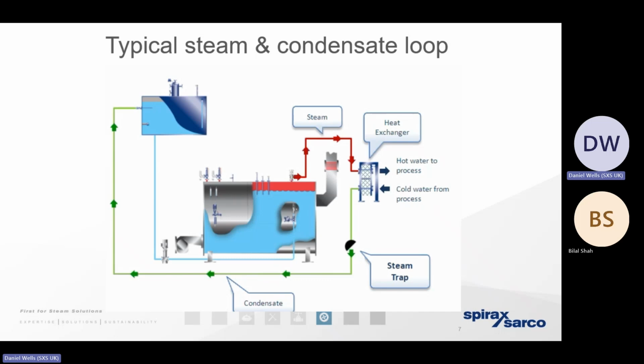very small pipe diameter. So if you think about the hospital up the road, or if you think at the chemical works down on Leeds Road, we could be distributing that steam thousands of meters. So if we can distribute high pressure steam with a small volume in a small pipework, there's a huge financial benefit to us. The other benefit of high pressure steam is we've got a lot of motive energy that is pushing the steam out of the boiler into the pipe and sending it thousands of meters to a plant room, to the point of use.